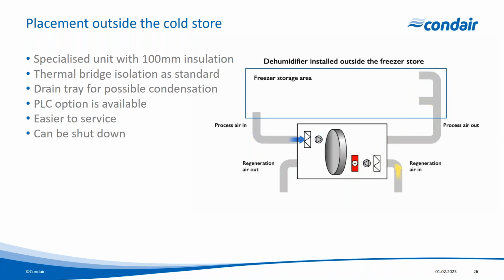Again, as we saw in the photograph, you should put it on a drain tray to make sure that any possible condensation that forms on the outside of the unit doesn't drip down and damage anything that's underneath it. But critically here, the PLC option is available. So you can optimize the rotor speed, optimize the heater, optimize the fan speeds with EC fans. So that makes it a more efficient system. And of course, it's easier to service because it's not in the freezer store and it's not taking up valuable space in the freezer store. And of course, it can be shut down and just dampers closed. So that is another option for you.